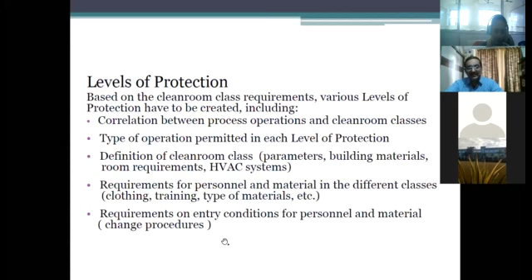All these are technical things which are to be designed so that your area is working efficiently. Otherwise, when you validate the area, it may fail. Right? So depending on the level of protection required, the whole area design and the processes will be designed like that. Requirements on entry conditions for personnel and material. The change procedures also will be arranged according to the level of protection required. So you'll have change rooms, you'll have crossover benches, you will have pressure cascades to maintain the level of protection.